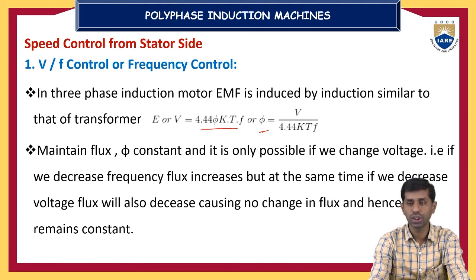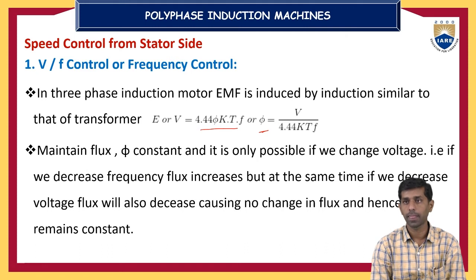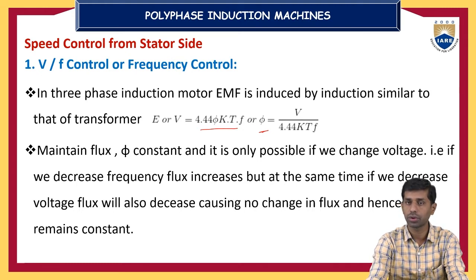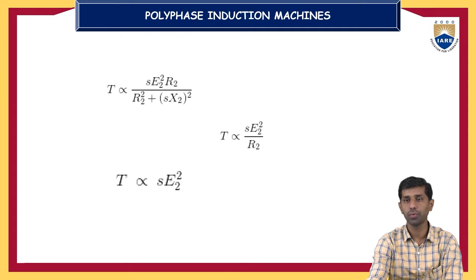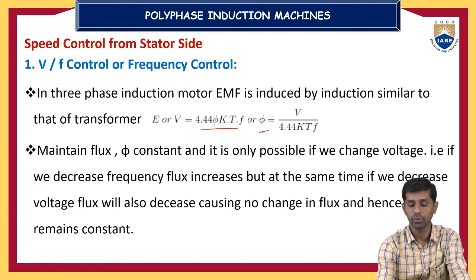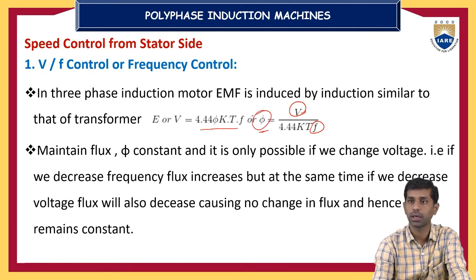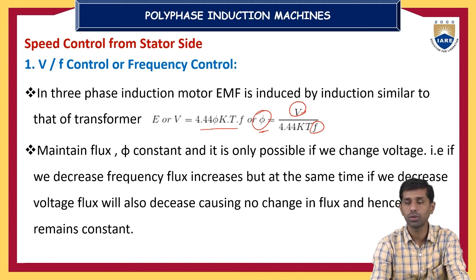If you change only the voltage or only the frequency, it will not give good speed control in V/f control. Changing only the frequency causes saturation effects in the stator and rotor circuits. To maintain constant flux, the V/f ratio must be kept constant. If you want to decrease frequency, you must also decrease voltage proportionally; if you increase frequency, you must increase voltage as well, so that V/f remains constant and flux remains constant.